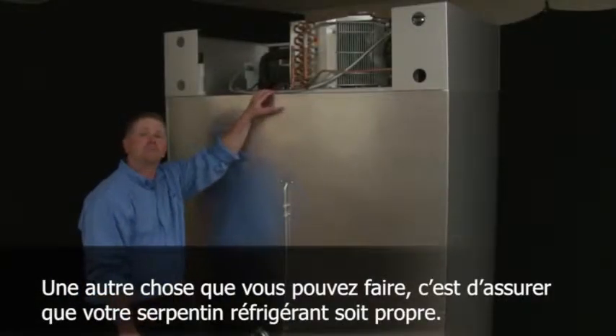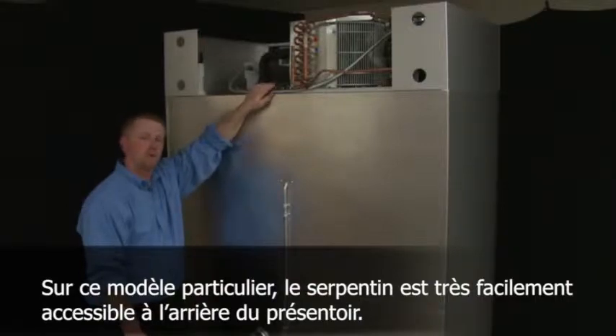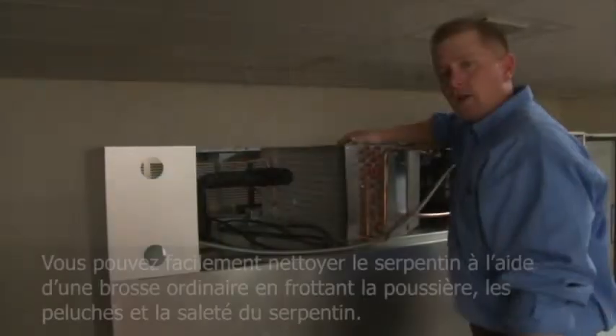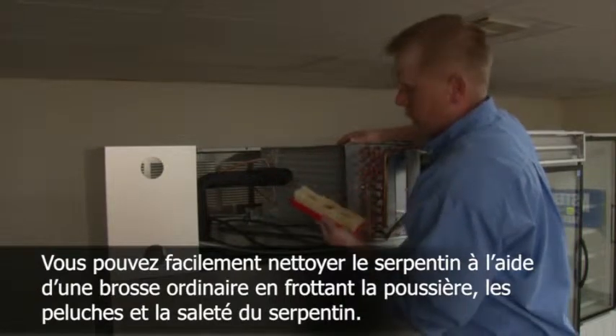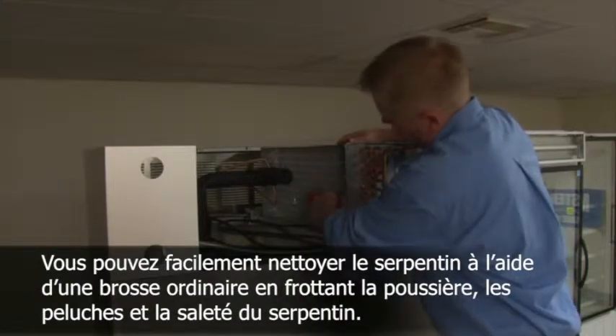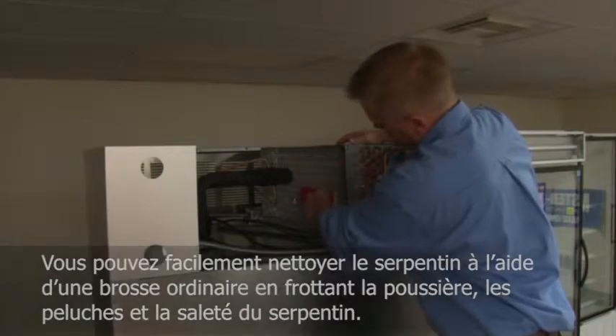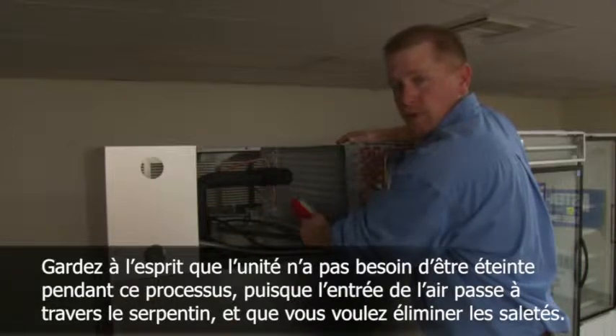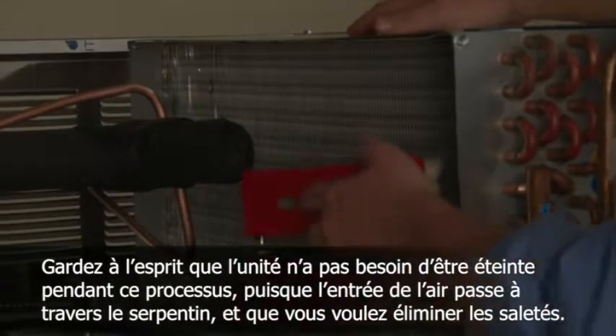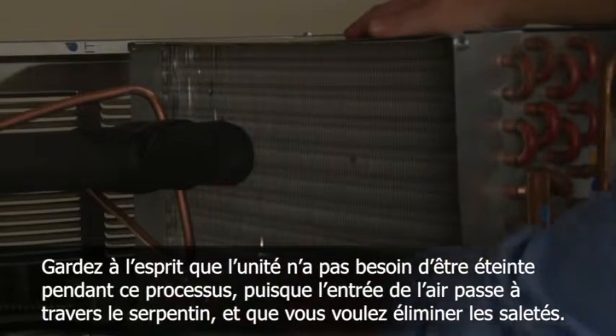One of the things that you can do is keep your condenser coil clean. On this particular model, the coil is very easily accessible from the rear of the cabinet. Cleaning can easily be done by using a normal everyday brush and brushing the dirt and debris down and away from the coil. Keep in mind that the unit does not need to be off during this process, as the air intake goes through the coil and you want to brush the debris out.